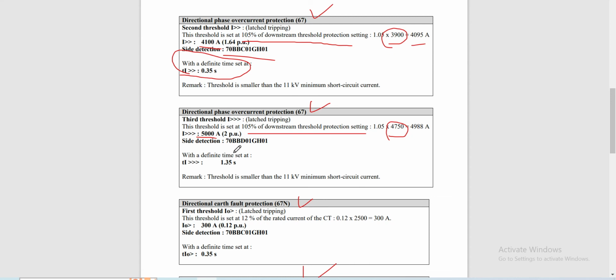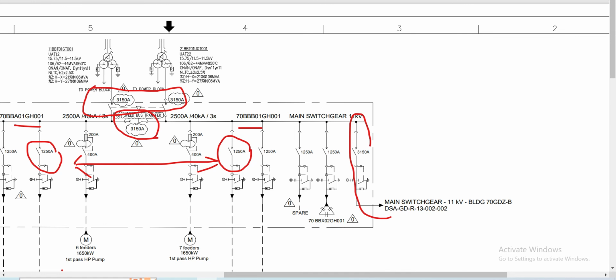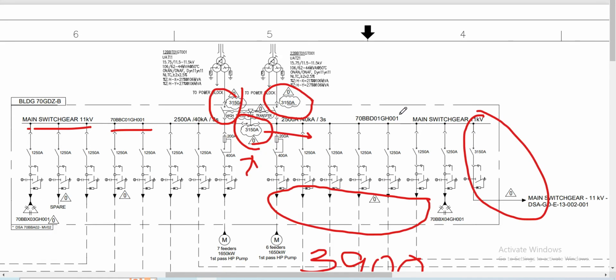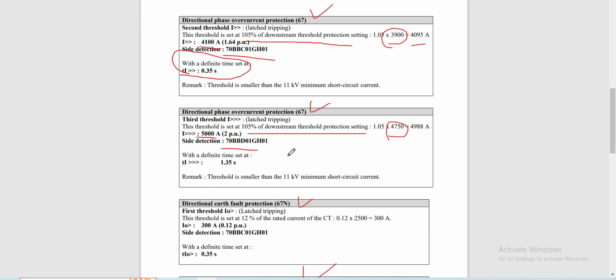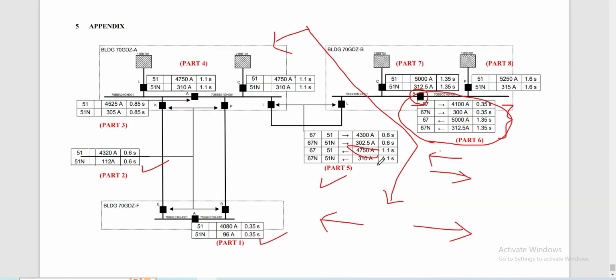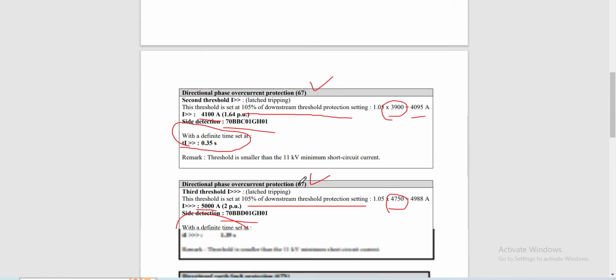The side detection is on the 70 BBD01GH01, this busbar from here. On our definite time setting, it is rated at 1.35 seconds. Since we are adopting this direction, we set this one at 1.35 seconds. That is for the overcurrent protection.